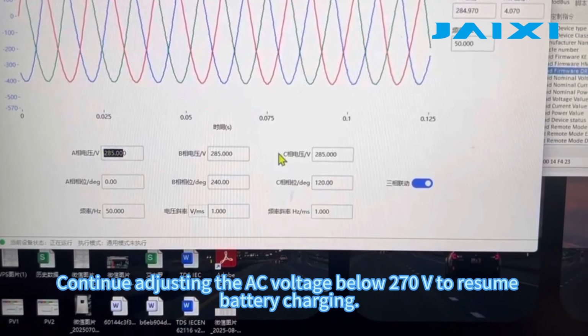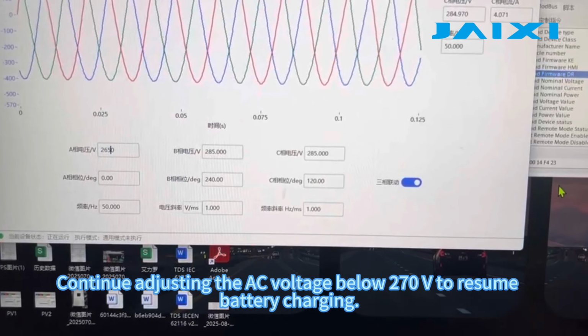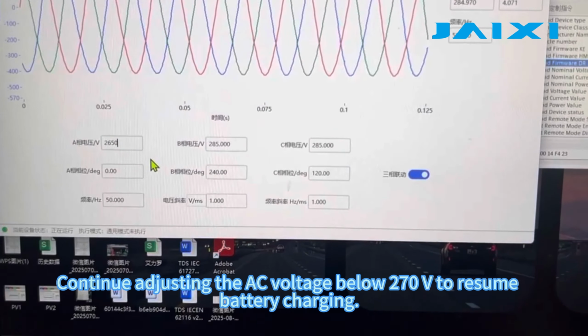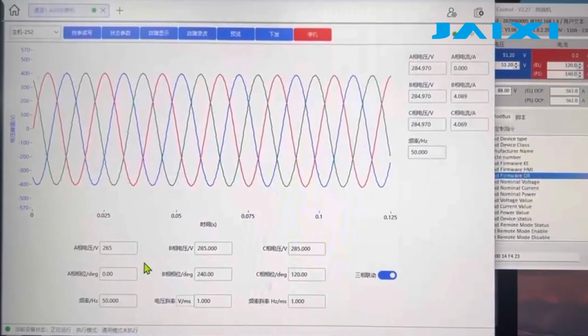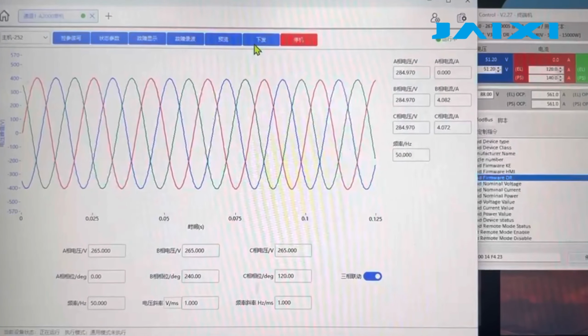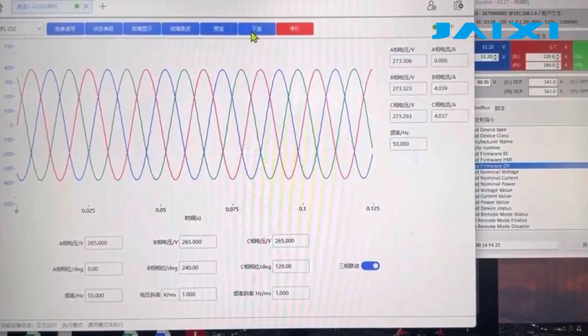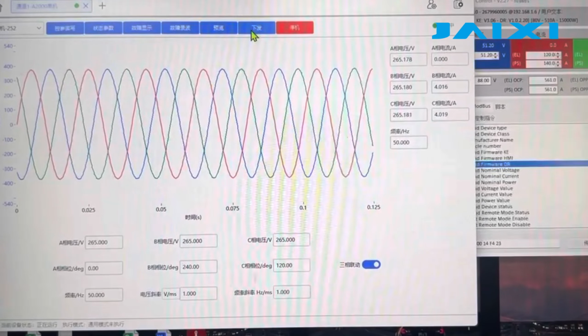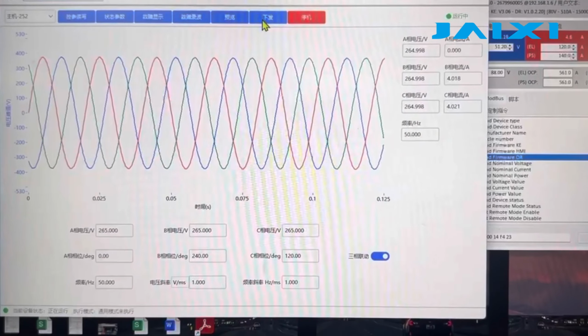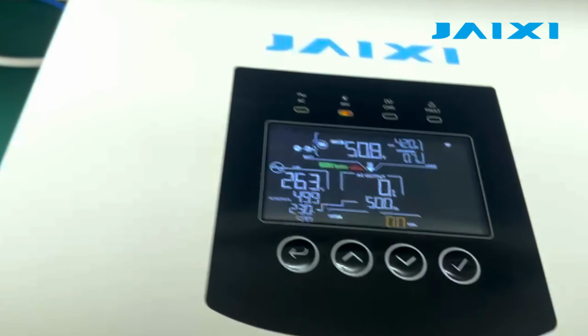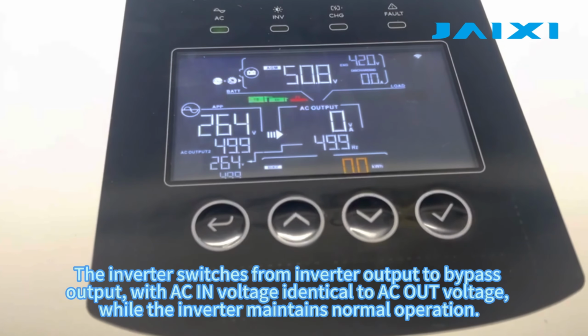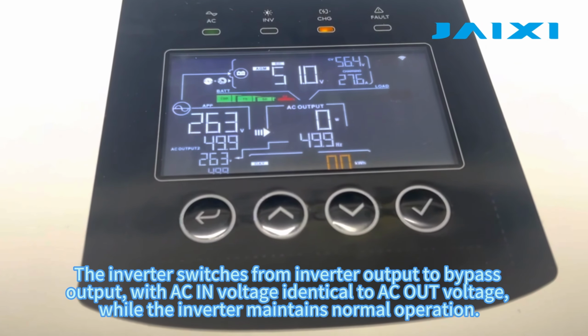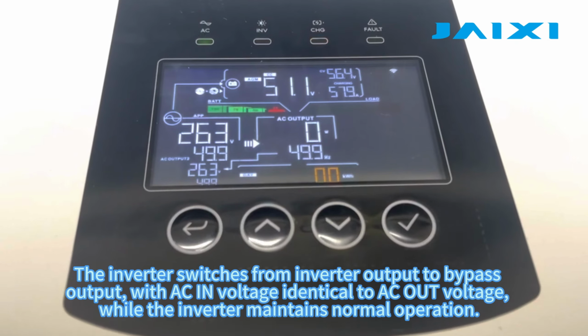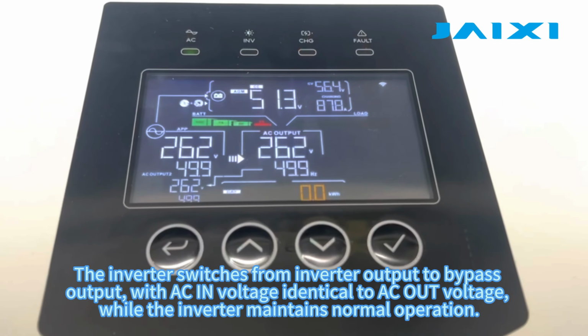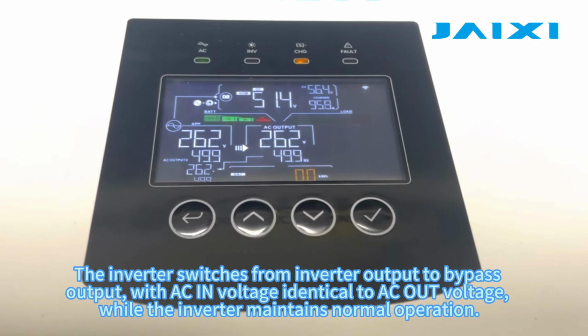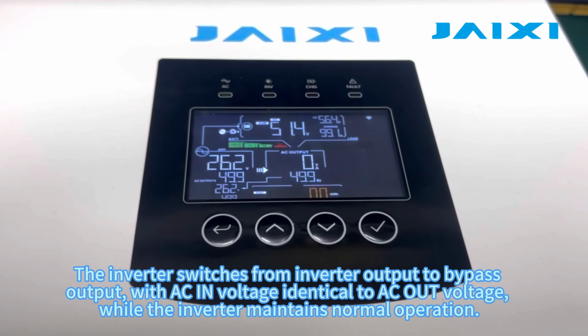Continue adjusting the AC voltage below 270 V. Resume battery charging. The inverter switches from inverter output to bypass output, with an AC in voltage identical to the AC out voltage, while the inverter maintains normal operation.